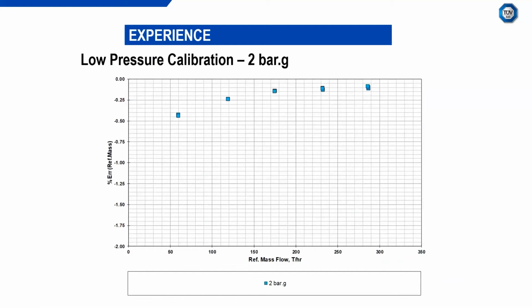So this is a low pressure calibration at NEL. On the y-axis we've got percentage error, the deviation between the flow meter and the reference, in this case the turbine meters. We have on the x-axis reference mass flow in tons per hour, and this is operating at 2 bar. Now you can see the performance isn't fantastic. It's fairly repeatable, but it's outside of specification for the first calibration.